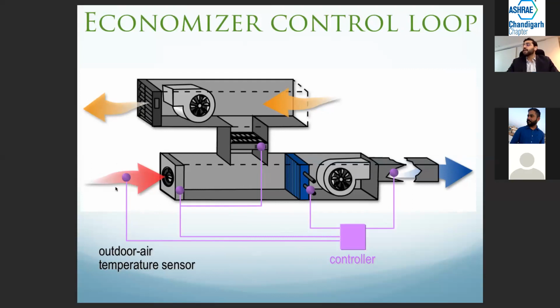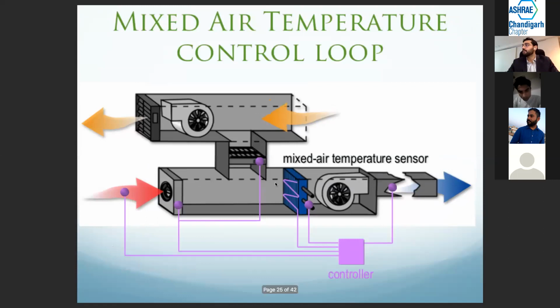Now we're going to add an outdoor air temperature sensor. We'll do something called economizing, also called free cooling. In scenarios where the temperature outside is nice enough, you can satisfy space temperature either by just modulating the outdoor air and mixed air, or by tempering the air a bit. Ideally, you could even use just the outdoor air to cool or heat the space, whatever is happening. And if not, the controller will modulate the dampers to achieve the desired temperature with the input from the outdoor air.